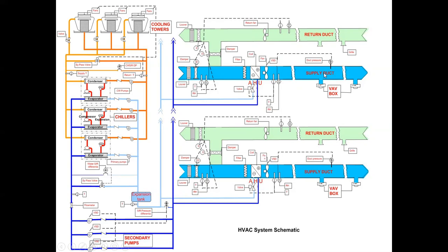For air conditioning, we're going to be looking at probably 54, maybe 52 starting to get really cold. Because what happens is if you don't insulate really well, you'll get condensate on the outside of the duct. It's hard to get perfect insulation. So any of the outside air on the outside of the duct, which is typically warm and fairly moist, gets up against that cold duct surface, the moisture condenses and it drips.